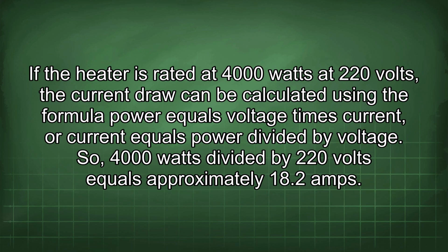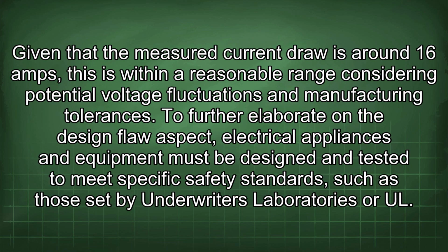If the heater is rated at 4000 watts at 220 volts, the current draw can be calculated using the formula power equals voltage times current, or current equals power divided by voltage. So, 4000 watts divided by 220 volts equals approximately 18.2 amps. Given that the measured current draw is around 16 amps, this is within a reasonable range considering potential voltage fluctuations and manufacturing tolerances.